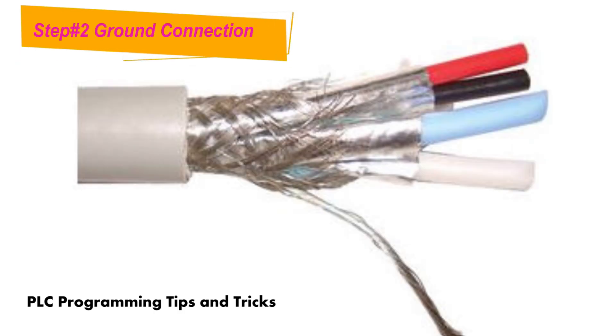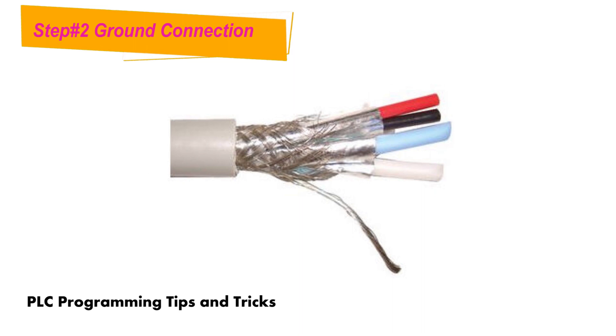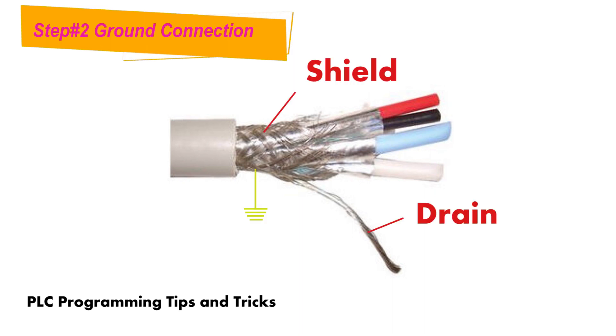Network grounding: the DeviceNet cable must be grounded at only one location. This should be done closest to the center of the network. Connect the network shield and the drain wire to an earth ground using wire up to a maximum of three meters in length.